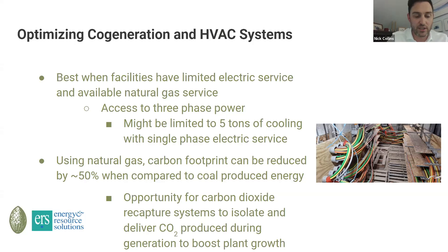So you have to have something to do with that waste heat in all conditions. One of the things you can do with that waste heat is put it through something called an absorption chiller. This would be a tri-gen facility where you're making heat, making power, and taking some of that waste heat and putting it through absorption chillers. It is an end use for excess waste heat if you had nothing else to do with it.